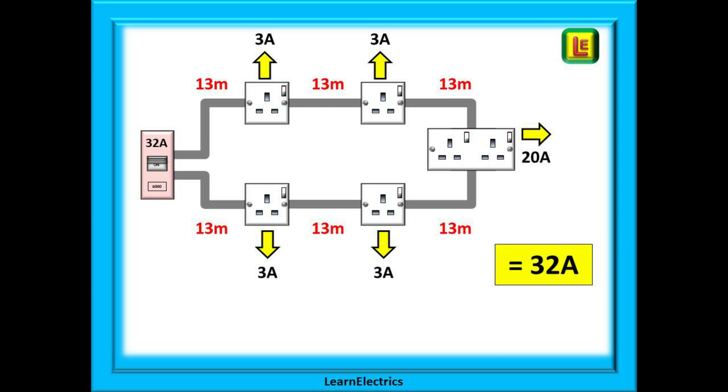Let us suppose that the circuit is fully loaded. We know that the furthest point, the double socket, will have a current demand of 20 amps in normal use, and that the remaining 12 amps will be evenly distributed around the ring circuit. That is to say each of the four single sockets will draw 3 amps per socket.